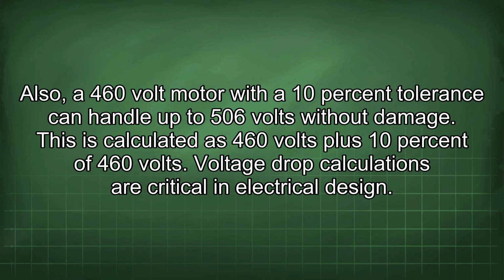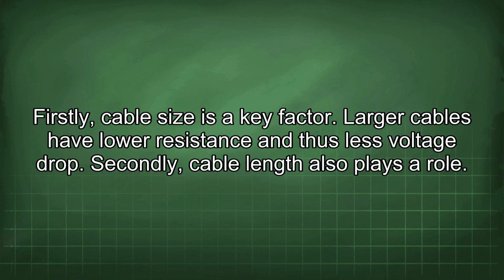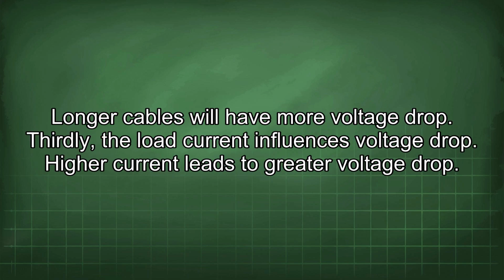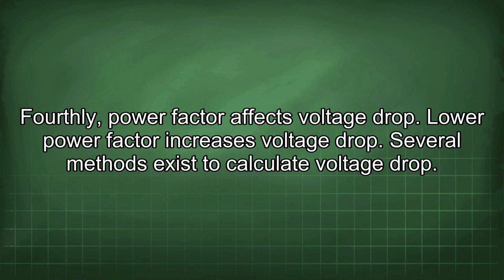Voltage drop calculations are critical in electrical design. Firstly, cable size is a key factor. Larger cables have lower resistance and thus less voltage drop. Secondly, cable length also plays a role. Longer cables will have more voltage drop. Thirdly, the load current influences voltage drop. Higher current leads to greater voltage drop. Fourthly, power factor affects voltage drop. Lower power factor increases voltage drop.